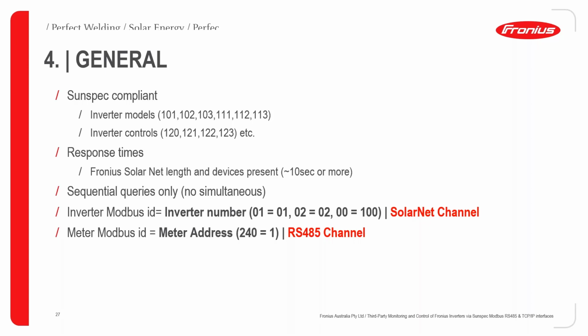Also, an important thing is that simultaneous requests are not allowed. You have to do sequential queries. This is a bit connected with the previous case where I said you have multiple loggers or controllers on the line. So you need to start thinking about, if you do have multiple masters in a way, or rather clients, which one has priority and which one can be excused, or maybe a bit of time in between is allocated.